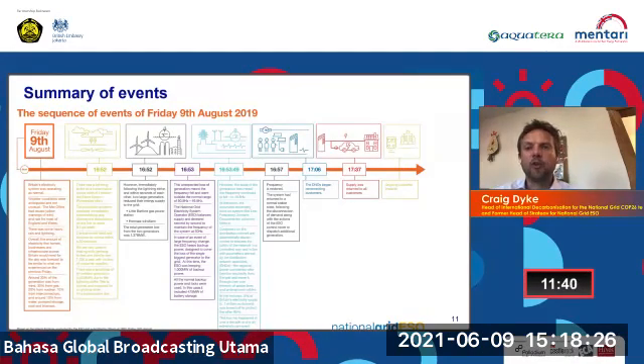In parallel with this, the control room had taken over 1,200 megawatts of manual action to restore that frequency, and 50 hertz was restored by 16:57. So from 16:52 through to 16:57, there's 5 minutes of activity that saw us restore the frequency back up to 50 hertz. At 17:06, the DNO began reconnecting customers. By 17:37, supplies had returned to all customers. That's 45 minutes of activity from a simple lightning strike, which would be standard, through to generation tripping off, the frequency falling, demand being disconnected, and then restoring all demand. So all that within a 45-minute window.